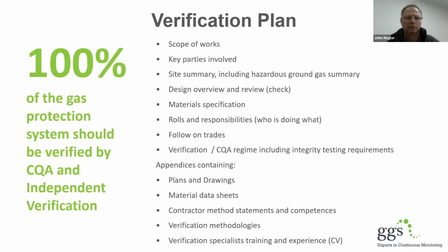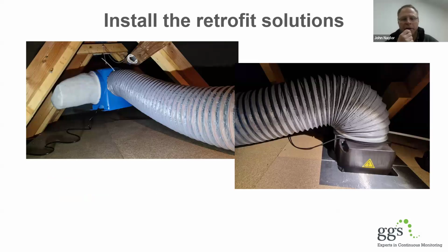So what can we do? Well, by far the vast majority of retrofit in the UK is for radon. And you can see things like this. This is a PIV, a positive input ventilation system. These typically go in loft spaces, as you can see in this particular example. It filters air, hopefully clean air, that's brought in. It pushes that down into the building and creates a positive envelope within the building, so long as the windows and doors are closed on the external frame. But even if they're open, it's still providing some fresh air.